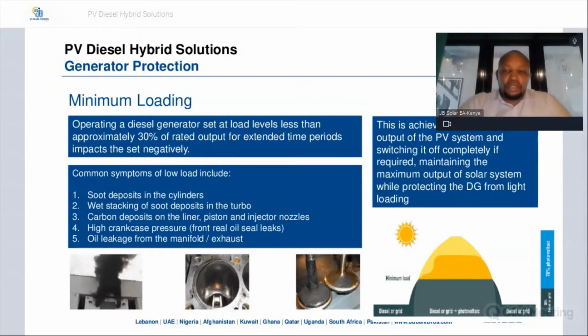So protection, generator protection when it comes to minimum loading. Minimum loading in generators is where you cannot go beyond a certain limit in relation to the power rating of the generator, and this is usually between 30 and 40%. And when you go below that minimum load limit, you can affect your generator negatively.